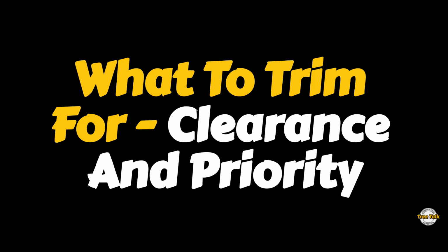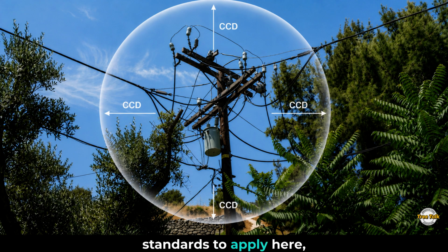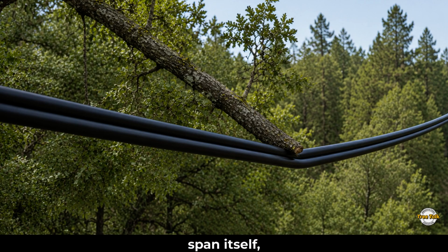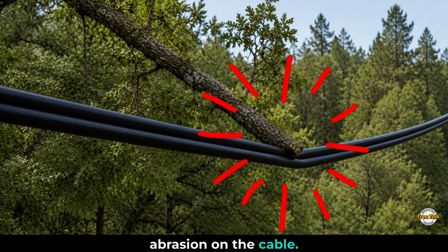What to trim for: clearance and priority. There are really two different standards to apply here, depending on what you're looking at. At the pole, hardware, transformers, and any other exposed equipment, we maintain CCD clearance. Along the aerial cable span itself, the standard is different. Since the conductor is covered, our concern isn't a strict clearance distance, it's making sure no tree or branch is causing strain or abrasion on the cable.